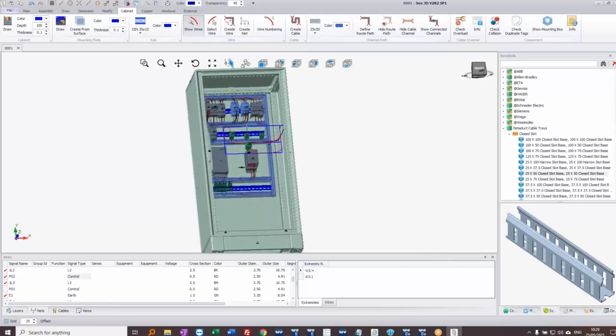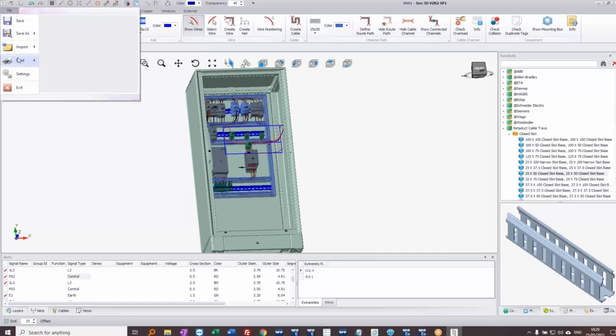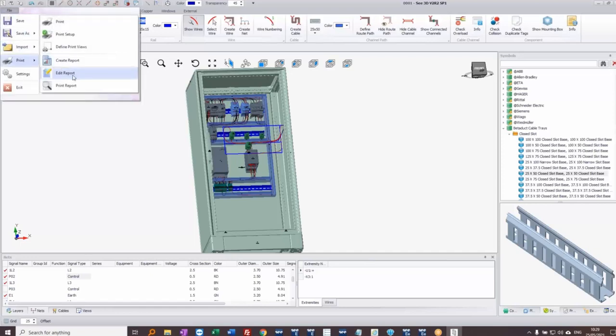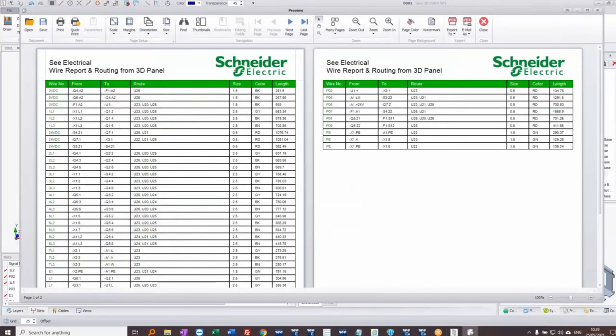With that wiring information, we can check it via a report. Under File > Print, I can print a wire routing report. This generates a nicely formatted report listing all wire numbers, what they connect from and to — showing the component name and connection point — the route through each named cableway, with multiple cableways separated by a comma, and then the wire size, color, and length in millimeters.